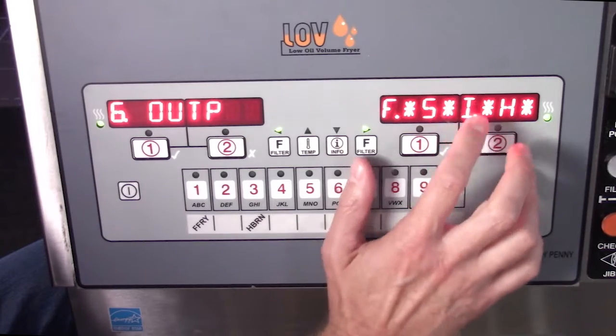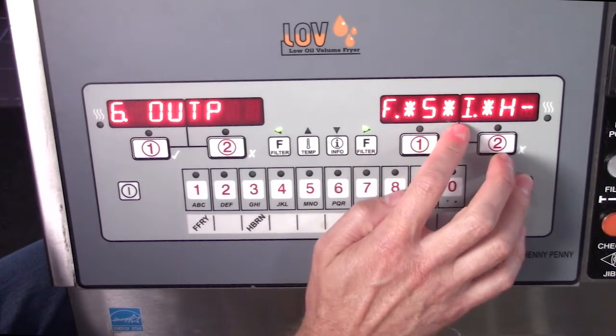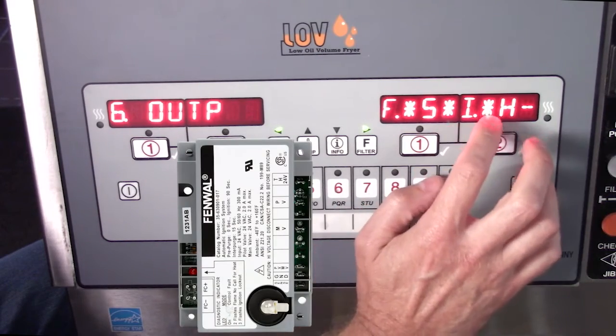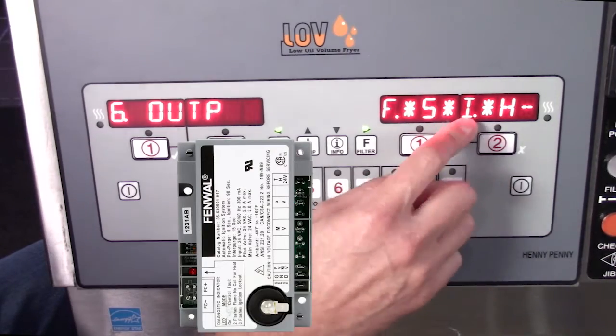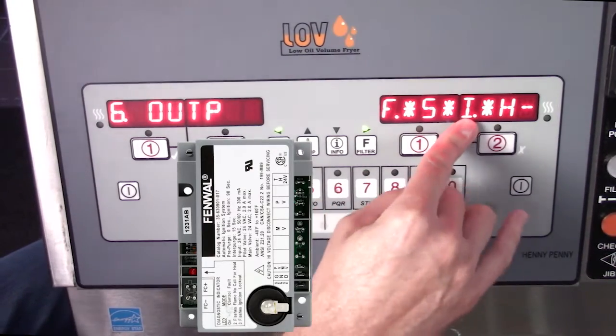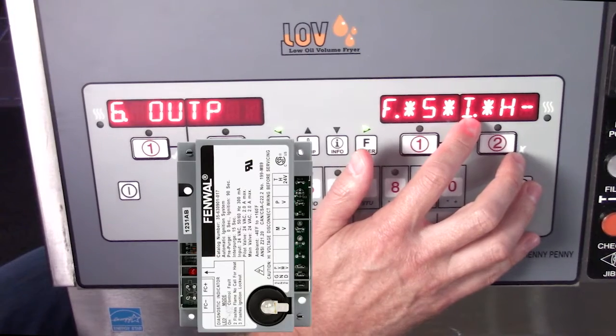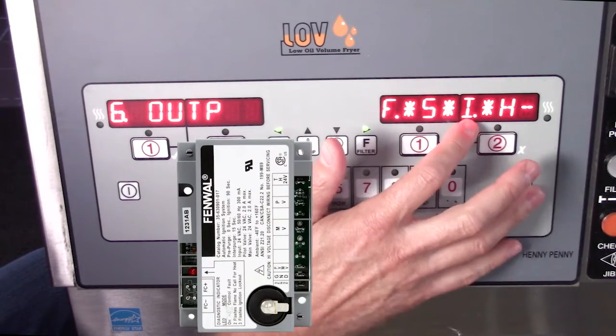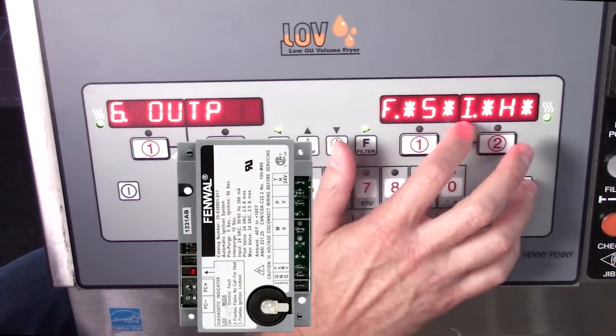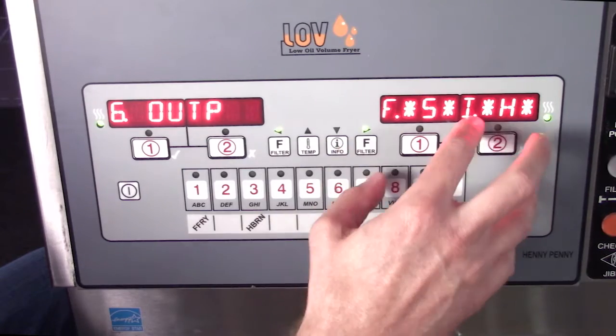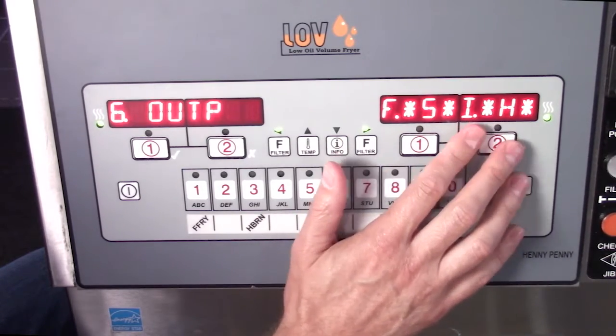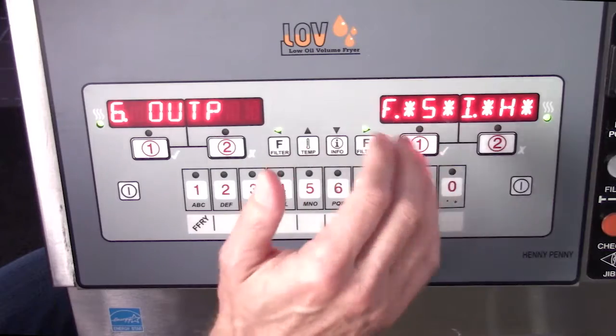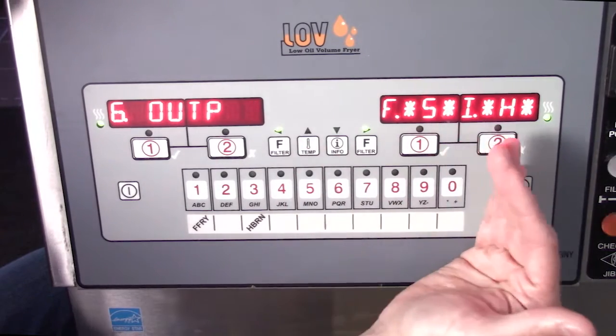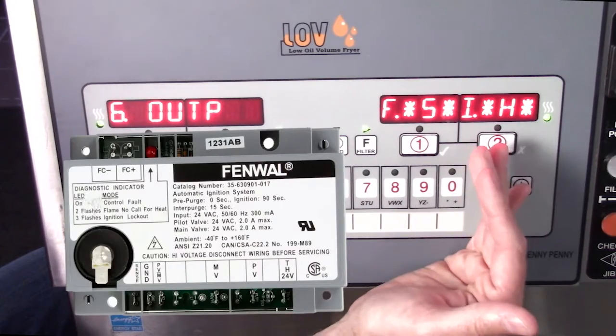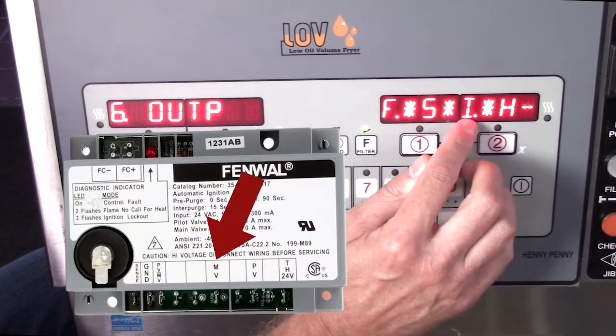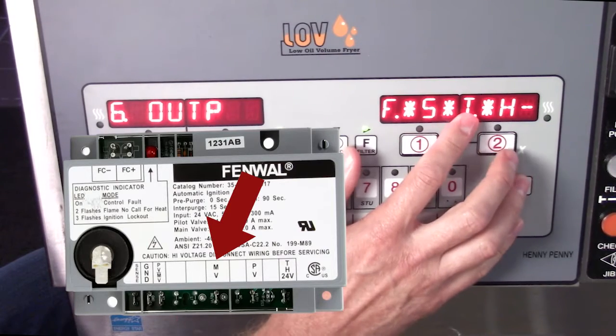Now the I is for my ignition module. So I've started my ignition sequence. That's what the little asterisk is telling me. The decimal here is telling me that the flame sense has been met. Now I say that, but in reality, it's telling me that I have flame sense, but the only way that I'm going to get this decimal to come here is I reach 1 microamp of flame sense from my pilot, which then is going to allow the 24 volts to come from my ignition module and go out to my control board.